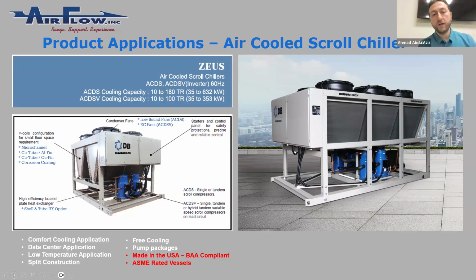The V just indicates that we are using VFD or inverter compressors. If you don't have the V, that means it's fixed speed compressors. Both are the same, just the capacity changes. So with the variable speed version, the first compressor is variable speed and ramps up and down, while it's always working, and then additional compressor stages come on as your capacity needs increase.